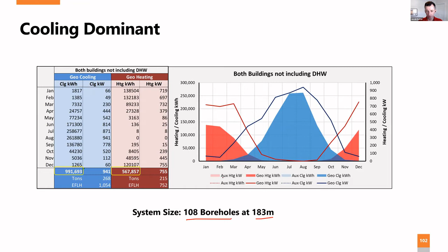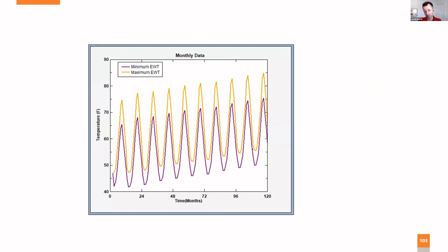So what we found is we needed 108 boreholes at 183 meters or 600 feet. And the ground temperature was actually going up over time. So we would have had to increase the spacing or add more boreholes to make it more stable. But instead, what we did is we added domestic hot water demands, the preheat for the domestic hot water, to the ground loop. And so we basically create this much bigger heating demand. And so now our heating is bigger than our cooling.